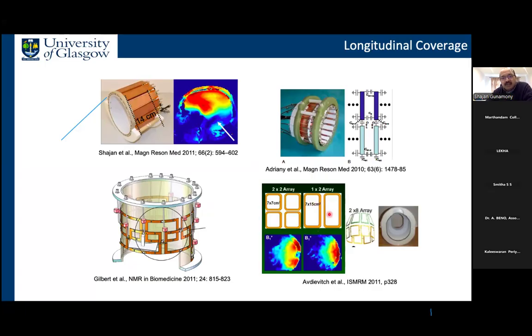So this is a 1x2 coil where the coil is long along the Z direction, and obviously it will then produce a field which is stronger in the center of this coil. So that's what you see in this plot here. But if you then break this up into 2x2 instead of 1x2, then you alter the spatial distribution of this B1 field, as you see here. That means we are now extending the longitudinal coverage.